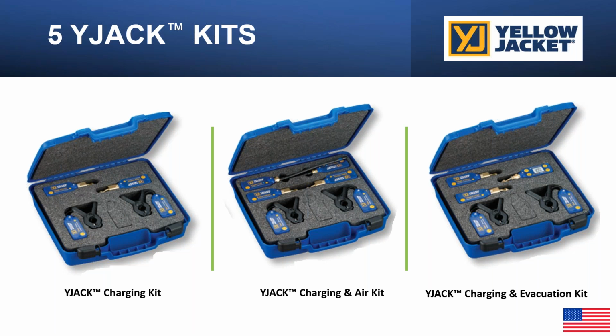Then you have a charging and evacuation kit. This kit is identical to the charging and air kit in the middle, but instead of two psychrometers, you now have a micron gauge. Unique to our micron gauge is that even though it's Bluetooth, it still has a readout screen on the device itself, so you could read it using the app or the digital manifold, or just look right on the micron gauge and see what micron level you've pulled down to.